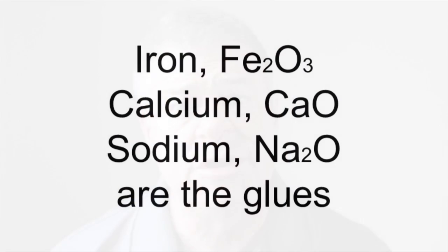But this carbon monoxide causes a lot of issues associated with slag and corrosion. Also, if you don't burn the sulfur, you get a sulfide, and you can actually have sulfide attack on your water walls. So just in summary, it's the iron and calcium and sodium that we mostly worry about. They're the low fusion or fluxing type elements. And then the elements like silica and alumina are the rock type materials.